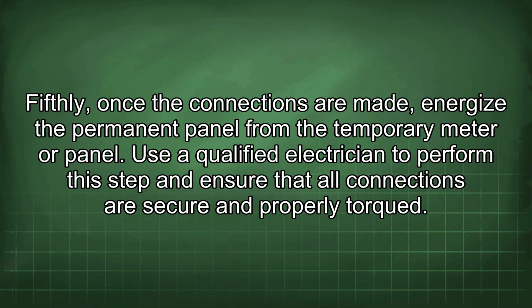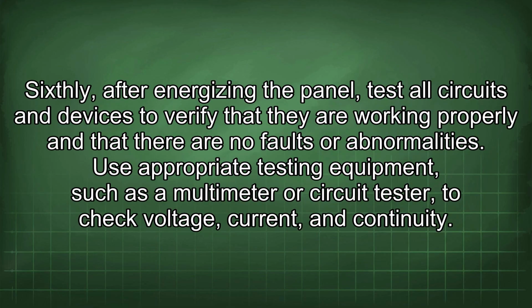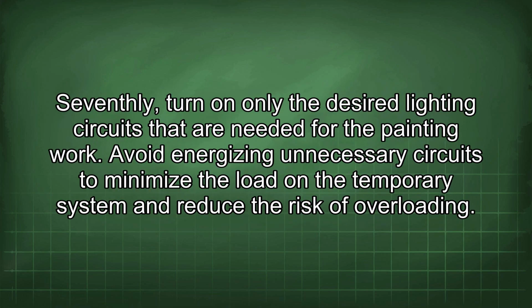Fifthly, once the connections are made, energize the permanent panel from the temporary meter or panel. Use a qualified electrician to perform this step and ensure that all connections are secure and properly torqued. Sixthly, after energizing the panel, test all circuits and devices to verify that they are working properly and that there are no faults or abnormalities. Use appropriate testing equipment, such as a multimeter or circuit tester, to check voltage, current, and continuity. Seventhly, turn on only the desired lighting circuits that are needed for the painting work. Avoid energizing unnecessary circuits to minimize the load in the temporary system and reduce the risk of overloading.